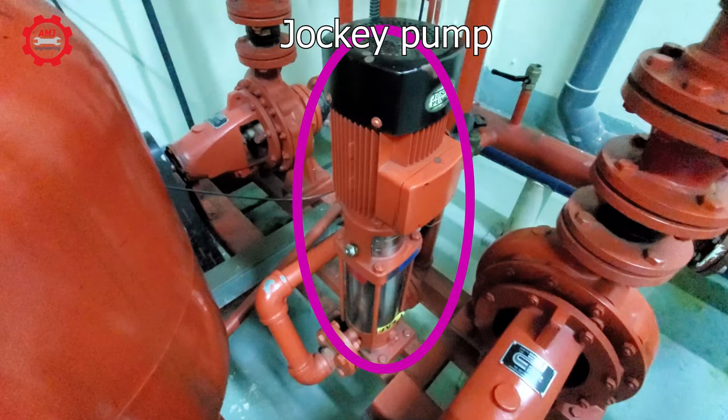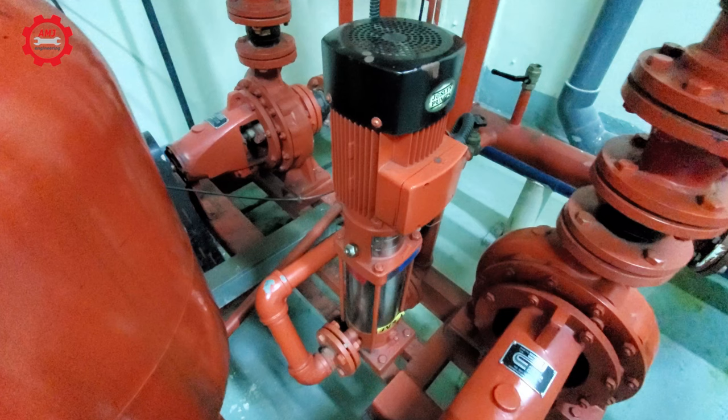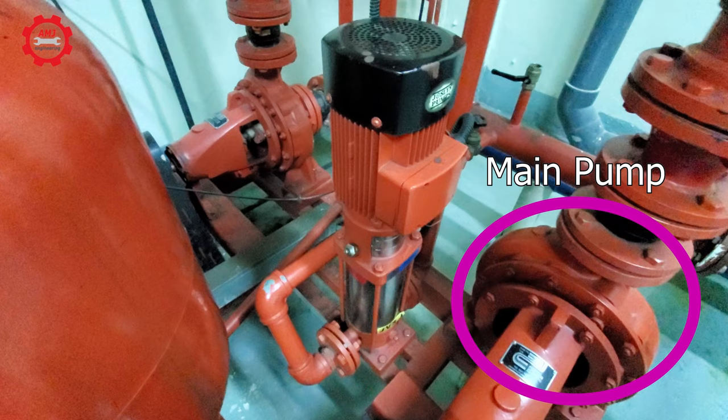Jockey pumps are small, motor-driven pumps used in conjunction with main fire pumps to compensate for minor leaks in the fire protection system and automatically maintain standby pressure. This reduces wear on the main pump and controller caused by unnecessary, frequent operation.